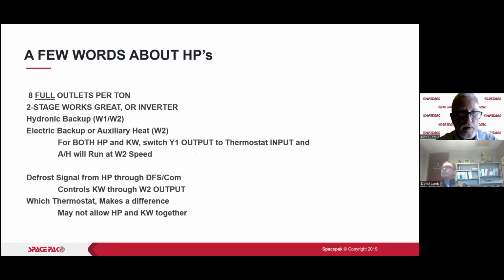All right, a few words about heat pumps. I mentioned earlier, 8 full outlets per ton. We are the condenser, if you will, in heating. So if we don't have an adequate amount of airflow over that hot indoor DX coil, then we could run the risk of going out on high head on our compressor, on our outdoor unit. Okay. Hydronic backup, W1, W2, electric backup for auxiliary heat. That's on W2, as I mentioned. And this covers that for both heat pump and KW switch: Y1 output, board output to the thermostat input, and the air handler will run it at the W2 speed.